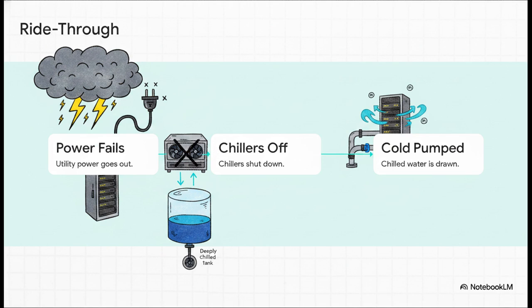Because the buffer tank is perfectly stratified, pumps can instantly draw the pristine, deeply chilled water directly from the bottom of the tank and send it to the air handling units. The servers don't even know the power went out. The cooling is completely uninterrupted.